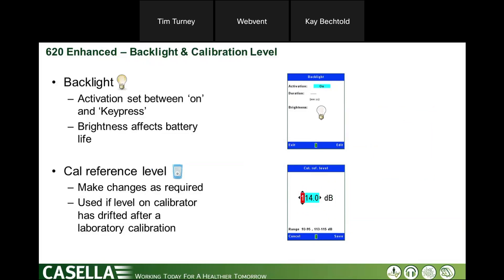For the backlight, you can have it switched on permanently or set it to activate on a key press. That way, if you leave it on a tripod for an area measurement over time, the display will time out to save battery life. Typical battery life with the display on is about 11 hours from three double-A batteries.